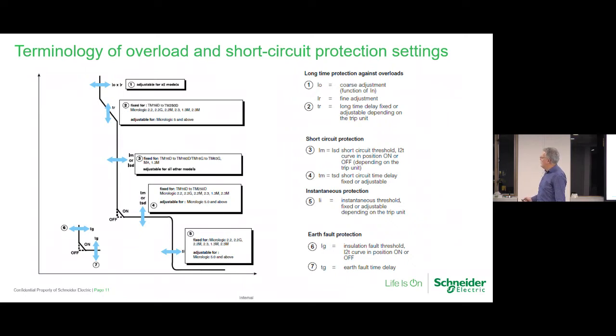And so the x-axis in time and current here, you're actually adjusting the curve up, away from, and giving a little bit added time for the downstream breaker. It's not showing it in here. Downstream breaker, time to trip. So time in thermal is a rare thing used. So if it's sitting there, all I would suggest you do is, because you're not really using it, you can actually push it out high. There's no, or low. Low is actually better, to be honest, for the network.